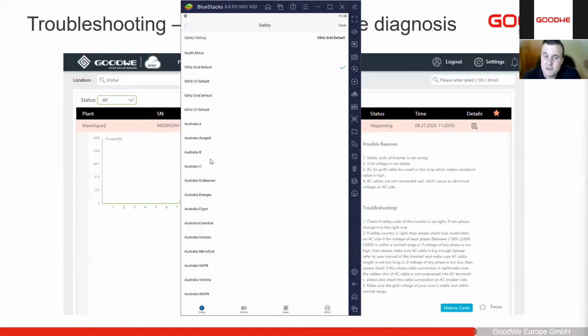So the hybrid inverters do have quite a lot of settings that you can configure from here. Please note this app is not designed to commission the system. It's only to change settings later on should you require, should something change on site and the customer needs to use different work modes or things like that. We're expecting a power outage and you want to make sure the batteries are full. All these kind of different scenarios that one has, this is what it's designed to be used for.